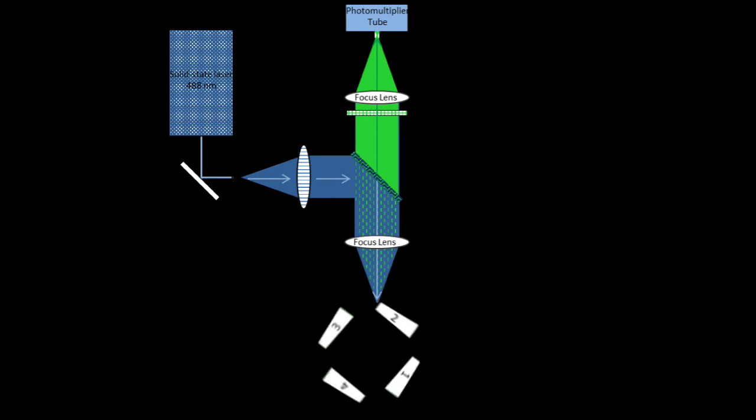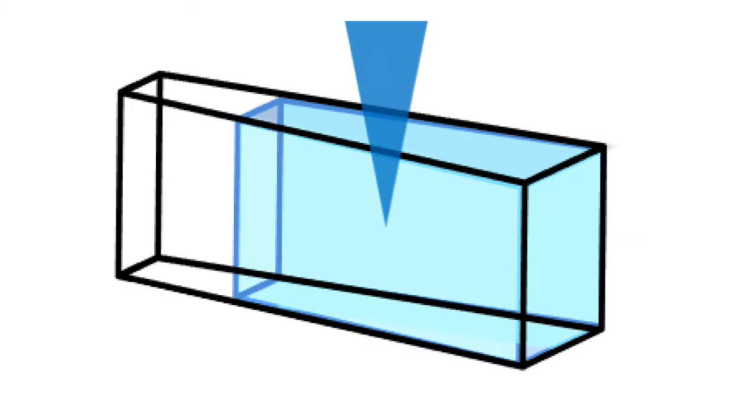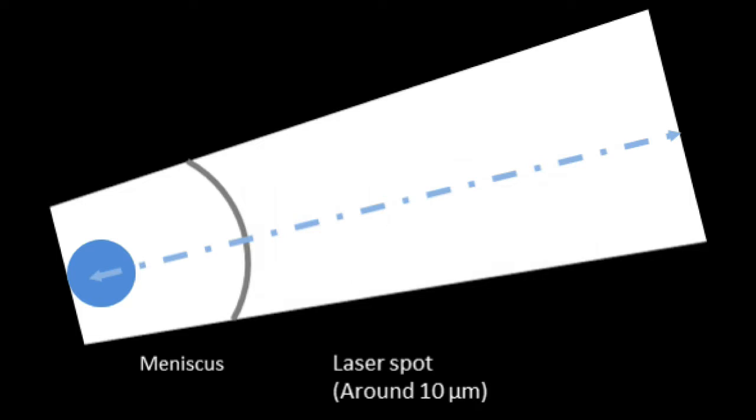The fluorescence detection system uses a confocal optical system to excite the sample and collect emission light. The laser light is focused into a laser spot around 10 micrometers at a specific focal depth. The focal depth is adjusted by software through a moving focus lens, up and down. With the moving of the optical box on a rail, the laser spot can excite samples at various radii in a radial direction.